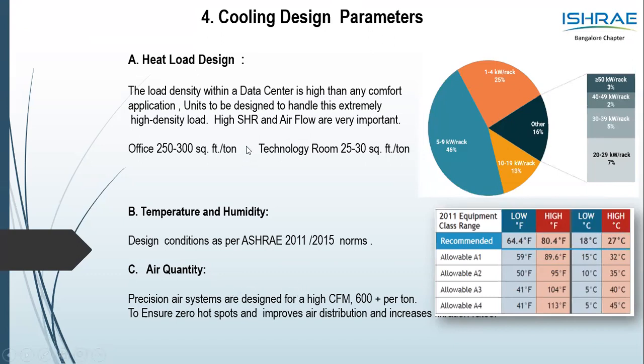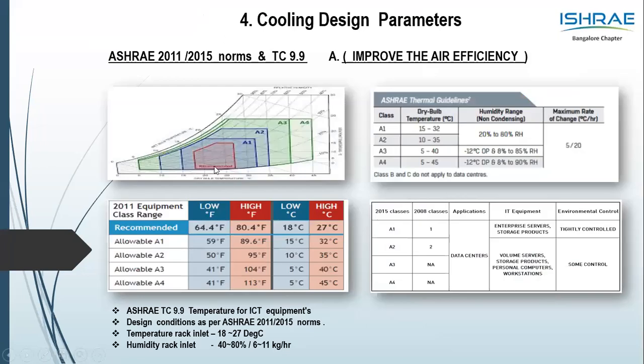And of course, the precision AC also comes with the benefit of higher CFM per ton, close to 550, 600, 650 per ton, which ensures zero hotspots and improves the overall air distribution within the server room. So let's talk more about this on the cooling unit. Referring to ASHRAE 2011-2015, the recommended temperature at the supply level is 18 to 27.